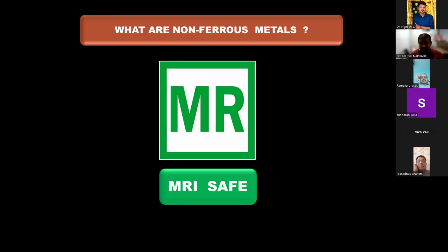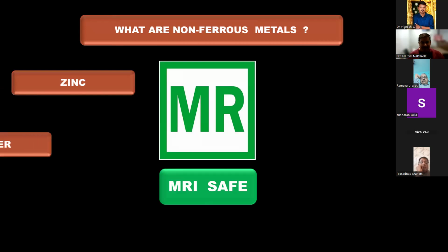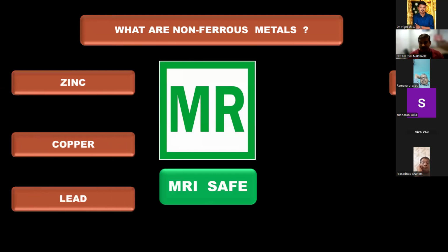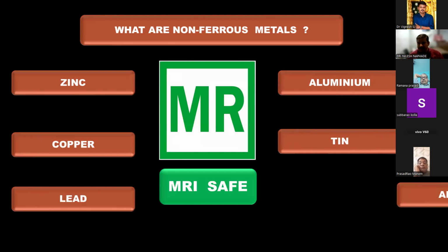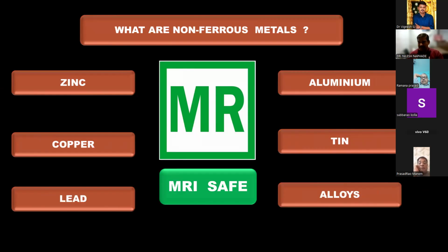So what are non-ferrous materials? What are these anesthesia machines, Boyle's machines, made of? They look metallic, but they are non-ferrous. They are MR safe because they are non-ferrous. So what are those materials? Zinc, copper, lead, aluminium, tin, or alloys. Alloys means mixtures of these metals. Anything made of these metals is non-ferrous, so it is not subject to the MRI magnetic field.